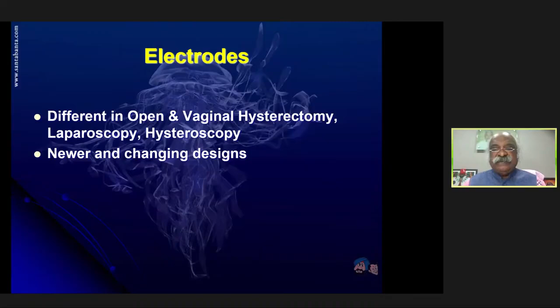Now coming to tissue effects and waveforms - continuous waveform versus interrupted waveform. The terms cut and coagulation are really a misnomer, dating from Bovie's time and Harvey Cushing. Bovie designed and named them cut and coagulation, but in fact they are all electromagnetic tissue effects varying based on the waveform. For example, cut is low voltage with an uninterrupted, continuous alternating current that is on about 100% of the time, so the total current is more over a given period, while the voltage is low.